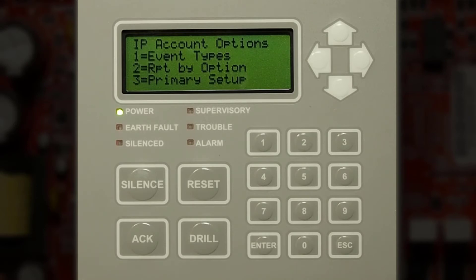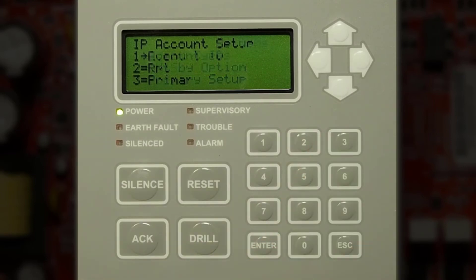You can change the event type. Event types would be whether you want to report alarms, troubles, and supervisories. Report by option would be whether you want to report by panel, zone, or point. Then primary setup would be the account ID, the DNIS, and the format of what you choose to send to the central station.